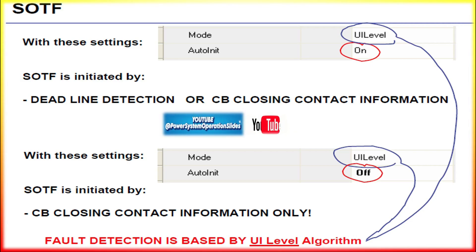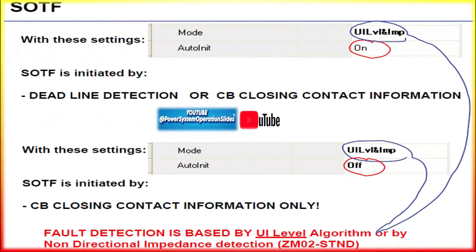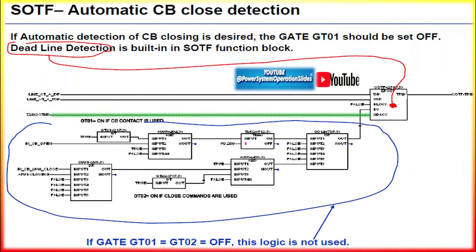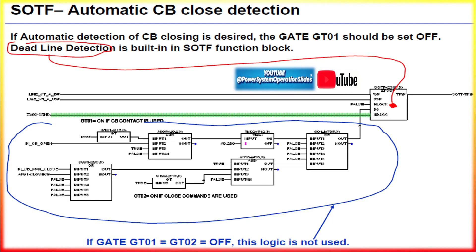Once the breaker closes and the circuit becomes energized, fault current flows immediately. The SOTF logic uses a high-speed current detection element that measures the fault current magnitude instantly upon breaker closure. The relay does not wait for zone-based protection calculations, which may take a few cycles; instead, it sends an immediate trip signal to the breaker if fault conditions are detected.